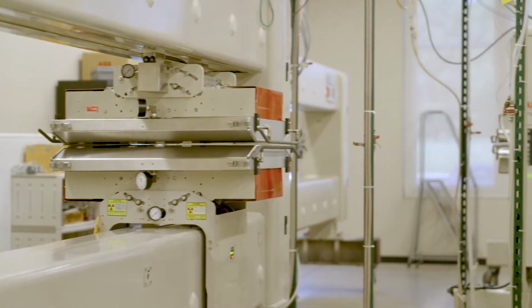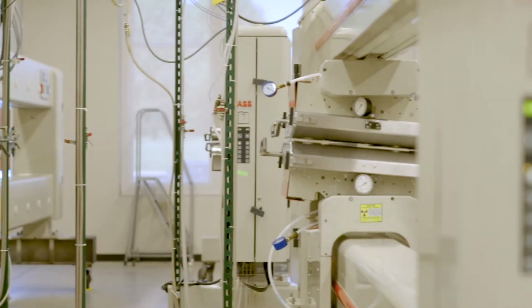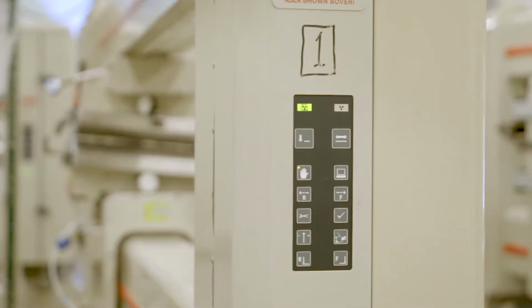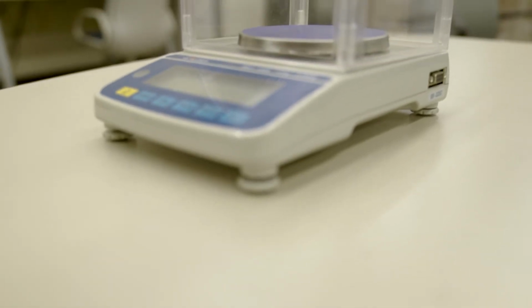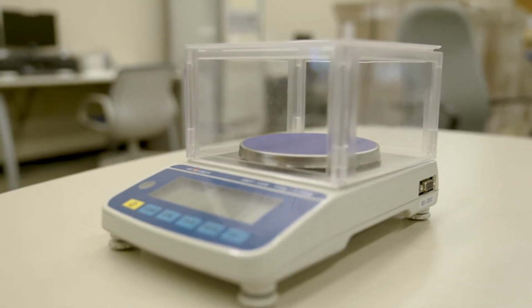In the paper making industry, sensor correlation is a comparison between the online sensors and the offline lab. When I talk about the online sensor, that's usually the sensors inside of a scanning platform. And the offline lab, we have a lot of standalone equipment in the quality control lab. So sensor correlation is about doing a comparison. When you have two watches, you don't know what the right time is, right? So typically we set one as a standard. Usually it's the lab. We make that our standard measurement, and then we correlate the online sensor measurement to match the lab measurement. That's our goal, and that is sensor correlation.